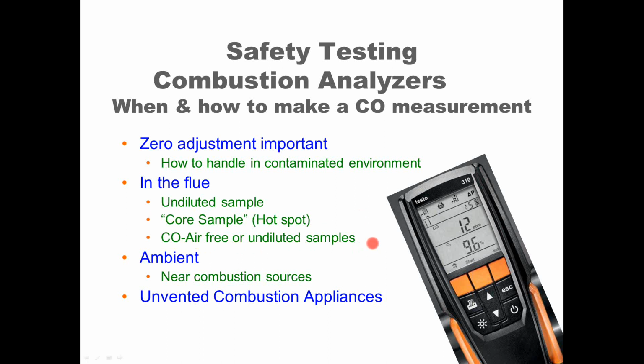And then you want to be taking CO air-free or undiluted samples depending upon how the measurements are being taken and how they're being used. The CO air-free is perhaps a better measurement because it's less dependent upon the amount of excess air, because it is subtracted out. We'll talk about how that's calculated in a minute. And then also measuring your combustion sources and unvented appliances, as we spoke about before.